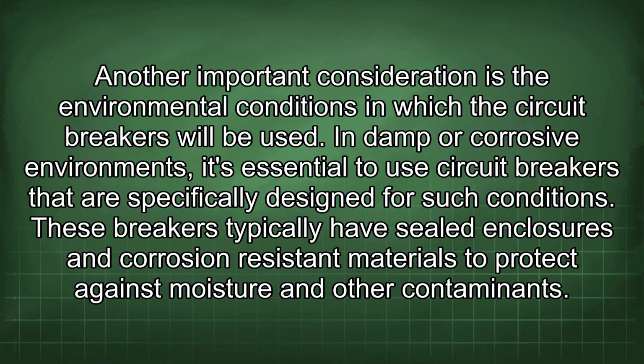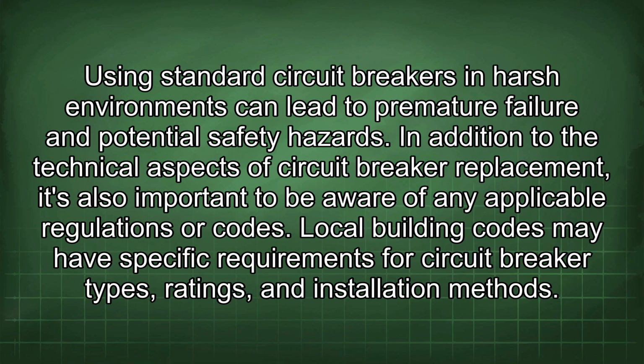Another important consideration is the environmental conditions in which the circuit breakers will be used. In damp or corrosive environments, it's essential to use circuit breakers that are specifically designed for such conditions. These breakers typically have sealed enclosures and corrosion-resistant materials to protect against moisture and other contaminants. Using standard circuit breakers in harsh environments can lead to premature failure and potential safety hazards.